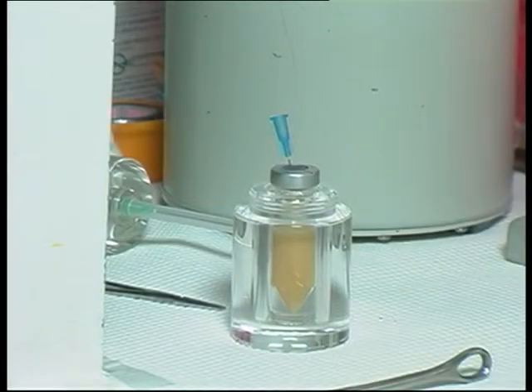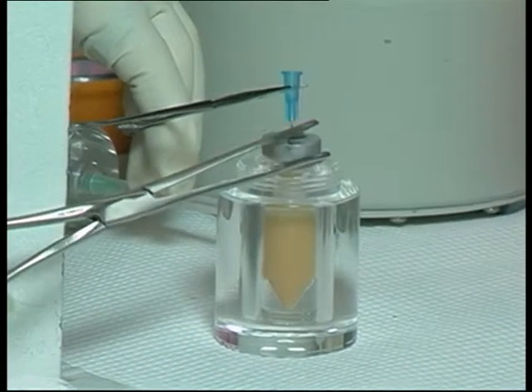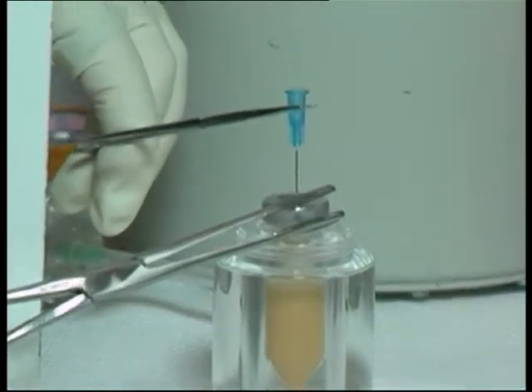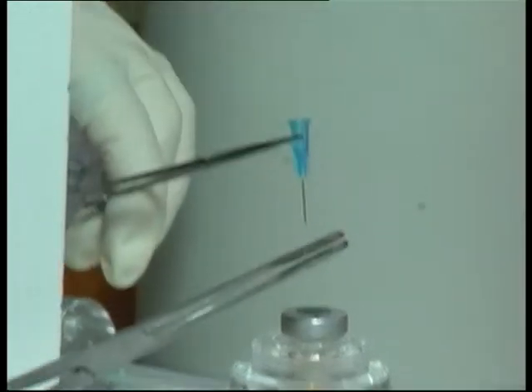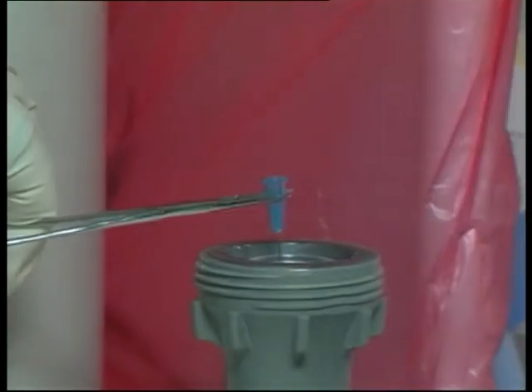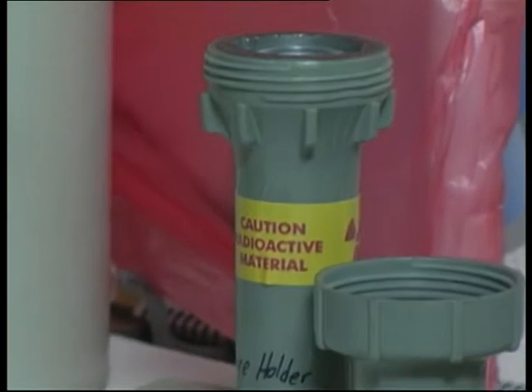Water for injection may have to be added to bring the vial up to 2/3, which will promote a homogeneous suspension and facilitate delivery. Use a remote handling tool to remove the venting needle. Dispose of the venting needle as radioactive waste.